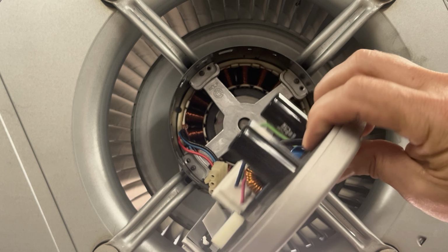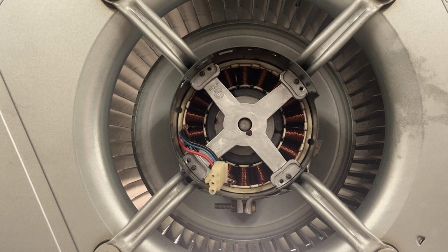You see a couple capacitors in there, and you want to make sure that you're not becoming part of any circuit. As you know, capacitors store energy and they release energy the moment you become part of the circuit. So you want to make sure that energy is discharged. So they're making sure that you're remaining safe too as you're in the field testing these components out. Sometimes your manufacturers want to know, is it a bad module or is it a bad motor? And you have to know which one it is.